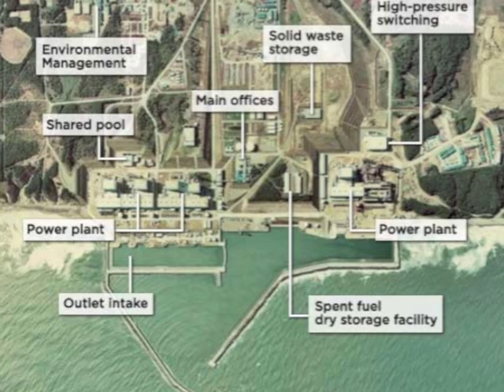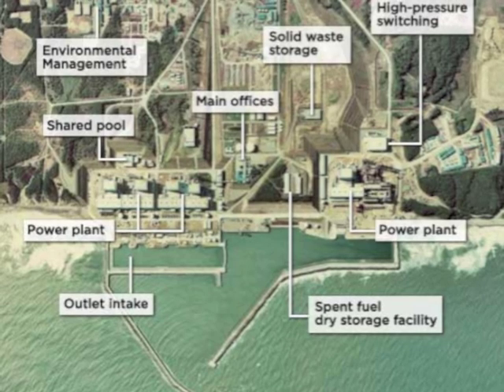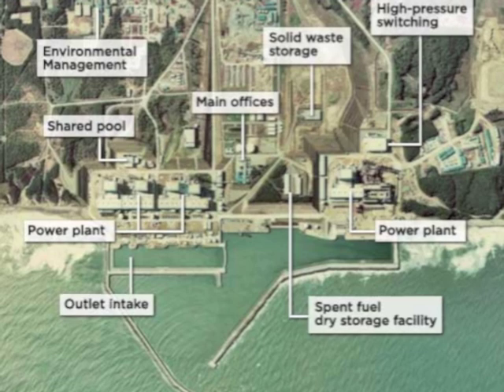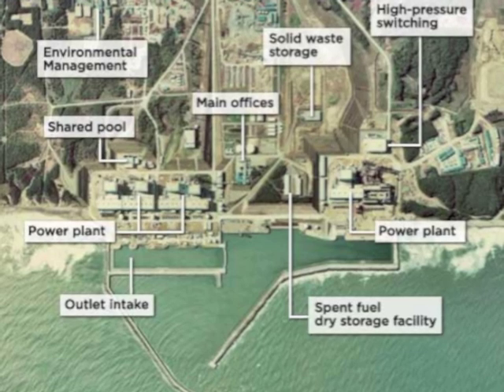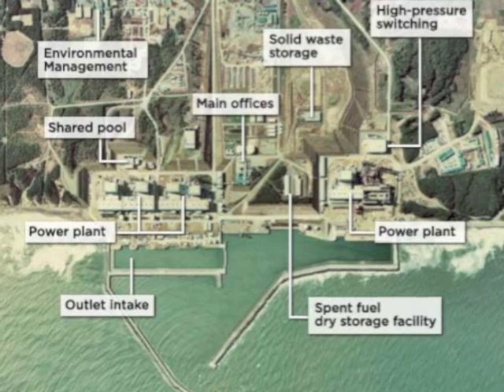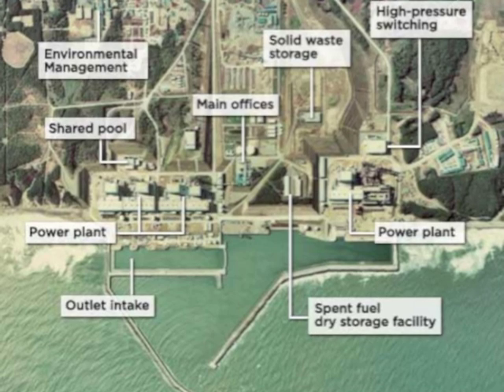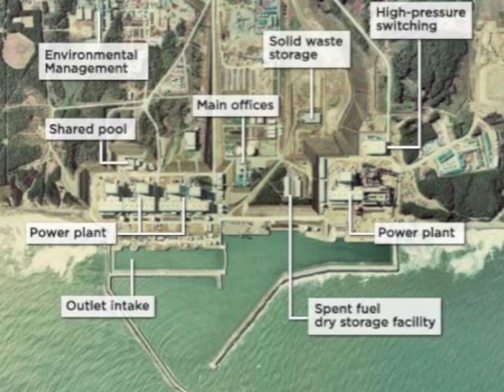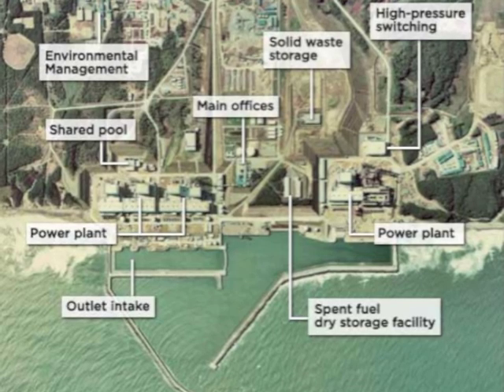That caused them to lose their diesel generator power and reduce them to their emergency battery backup power only, which wasn't quite enough to have the cooling capability that they needed. The emergency backup on the batteries gives them very, very limited capability. So they were having a very difficult time keeping the plant cool.